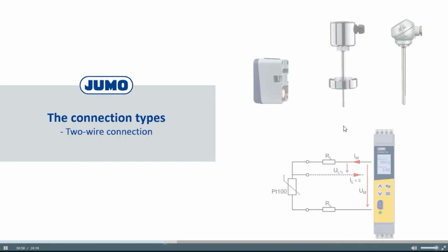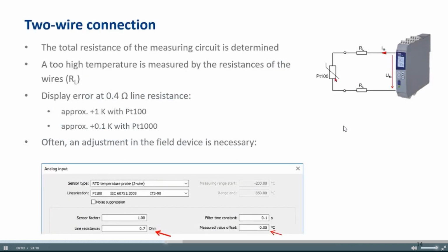So let's look at the different connection types. The 2-wire connection is the easiest way. Let's say we have a PT100. We connect it to our field device, and the field device measures and calculates the resistance. But here you can see the resistance which will be found is not only the resistance of the PT100. No, we always measure a bigger resistance because of the core resistances here. And if you have a PT100 and only 0.4 ohms of line resistance, which is not much, then your display will show a 1 Kelvin higher temperature. So we have a temperature offset for this PT100 of 1 Kelvin.